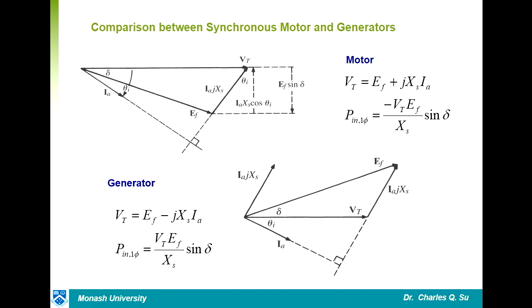But for your synchronous motors, normally you are inductive because you have a mechanical load, and your synchronous motor has a coil, the armature. So it's inductive. Your motor will absorb real power because you have a mechanical load on the shaft. You also absorb reactive power because of the inductance, the reactance of your armature. But in some cases, if I energize DC to your rotor with very heavy current, your synchronous motor absorbs electrical energy and converts it into mechanical energy, but at the same time I produce reactive power. So I supply reactive power at the terminal.